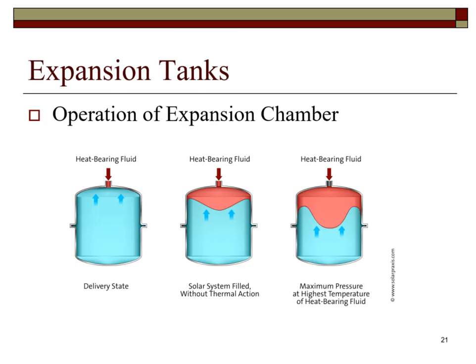The expansion vessel is a tank divided into two parts by an elastic membrane. On one side of the membrane is a corresponding operating fluid, normally water in a liquid state, and on the other side is air or an inert gas pressurized to the working pressure. The initial pressure is established at the factory and may be adjusted later during installation.